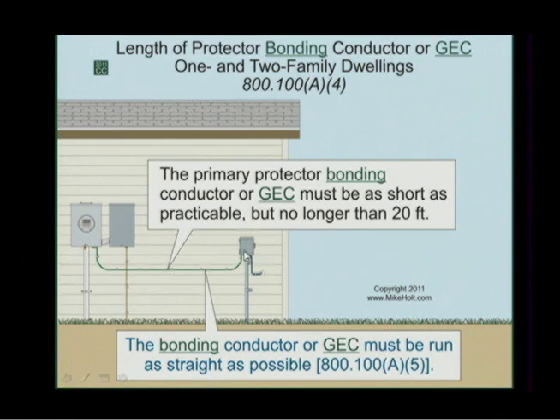We're trying to protect the equipment once you get in. We don't want 10,000 volts between the building ground and the telephone ground, so we try to get them together. The insurance industry pushed this a few code cycles back: make sure this bonding conductor is not more than 20 feet. And if it is more than 20 feet, you then drive a ground rod for the communications. Now you have a grounding electrode conductor. The code says in one or two family dwellings — they couldn't get this passed for commercial — you need to have it no more than 20 feet.